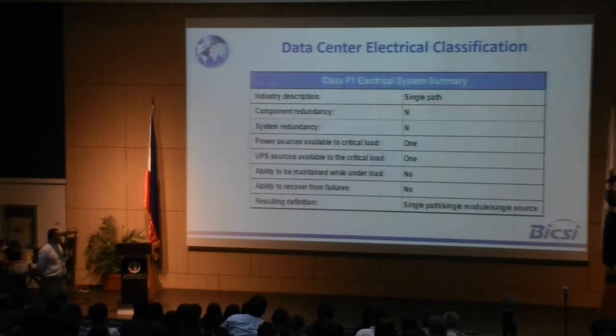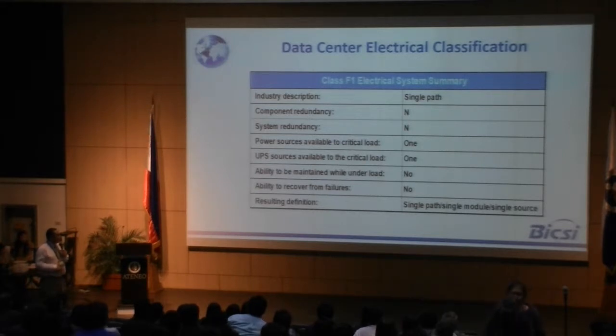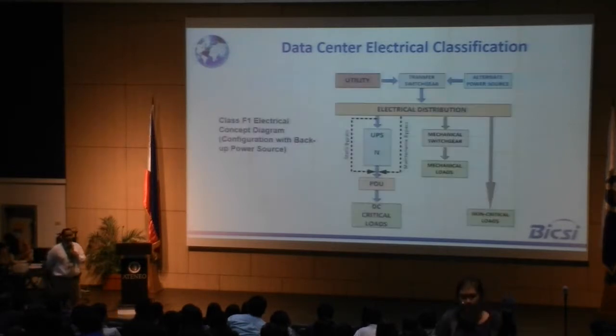So what's next? Class F1, still single path. Single path, single module, single source, but now there's an available critical load—UPS source available to critical load. Then system redundancy and component redundancy, what does it look like?